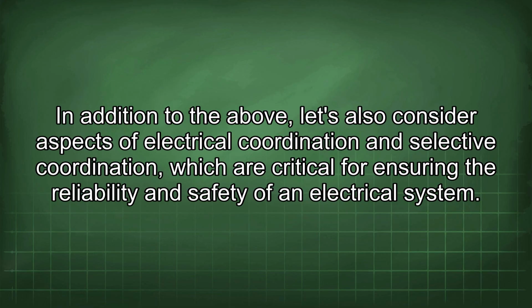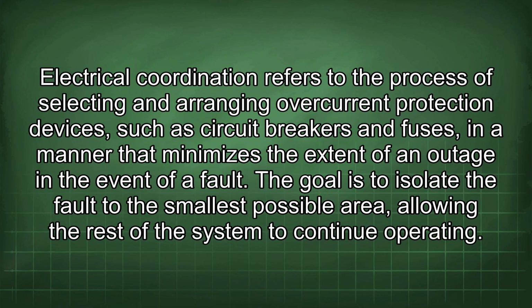In addition to the above, let's also consider aspects of electrical coordination and selective coordination, which are critical for ensuring the reliability and safety of an electrical system. Electrical coordination refers to the process of selecting and arranging overcurrent protection devices, such as circuit breakers and fuses, in a manner that minimizes the extent of an outage in the event of a fault.